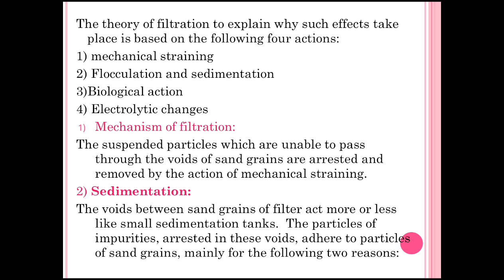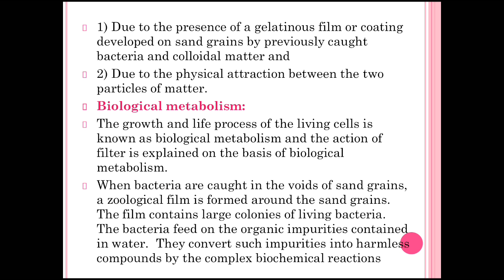The particles of impurities arrested in these voids adhere to particles of a sand grain, mainly for the following two reasons. First reason is due to the presence of a gelatinous film or coating developed on a sand grain by previously caught bacteria and colloidal matter. And the second one is due to the physical attraction between the two particles of the matter.